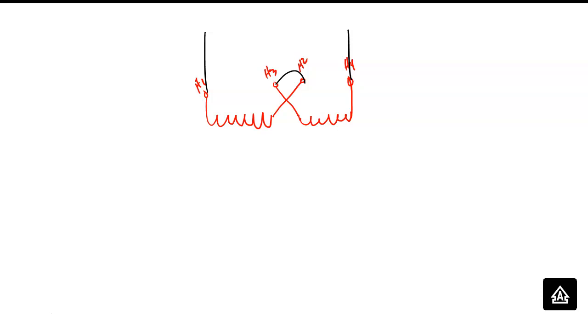For parallel, when we do this layout, we're going to wire the transformer. We'll start off wiring it for low voltage, then wire it for high voltage. We're not changing our 208 input, right? What's going to happen is we'll actually see the division ratio when we divide. It won't hurt anything. We're not going to skip the part where they say wire it for high voltage or low voltage, we're going to wire it for both so we can actually see it. Any questions on that?